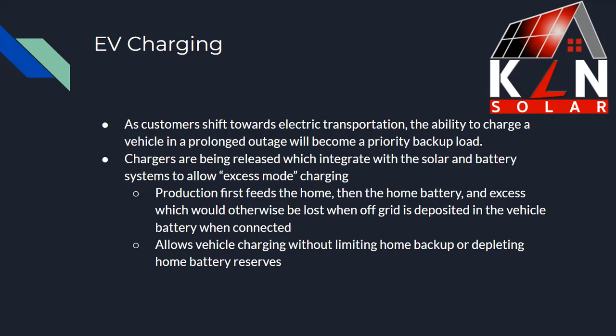The top one on the market right now is the SolarEdge charger—really the only one actively available. This EV charger integrates with the Energy Hub inverter and Energy Bank battery system. SolarEdge now uses the term SolarEdge Home to describe their whole integrated system. The charger connects directly to the inverter, which removes the need for an additional breaker on the main panel. That alone can sometimes reduce or prevent the need for a main panel upgrade or sub panel if your breaker box is already full.